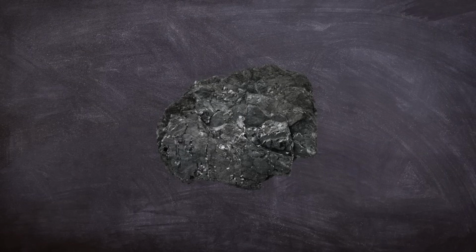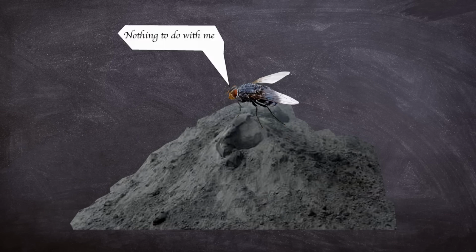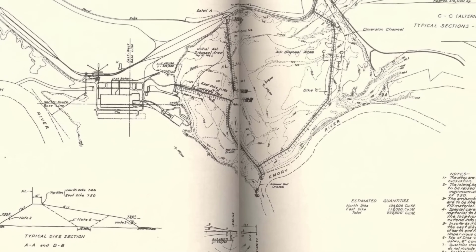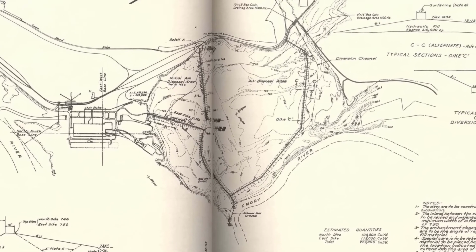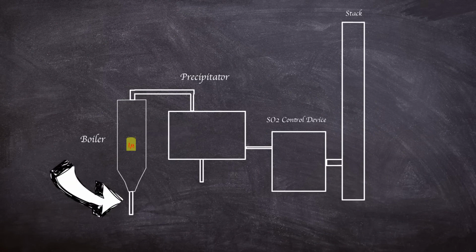Coal is a dirty fuel and, as such, has some pretty nasty polluting byproducts. Fly ash is a byproduct from coal burned in power generating plants. To stop this particulate matter getting into the atmosphere, a type of storage is needed to reduce the risk of environmental pollution. To achieve this, containment ponds are used. At full power operation, 1,000 tonnes or 1,200 cubic yards of coal fly ash is produced daily by the plant. The fly ash is captured by electrostatic precipitators and mixed with bottom ash, which is taken from the boilers.